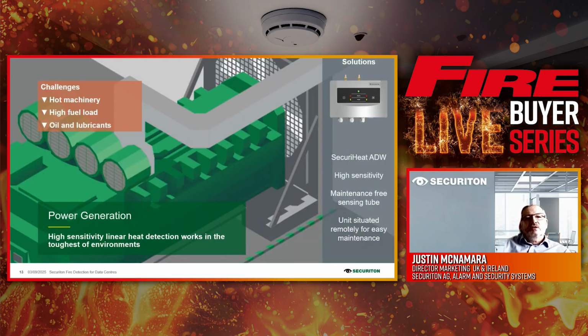There's also a challenge within power generation for data centers, usually a separate room or quite often a separate building. Within the power generation area, there may be hot machinery, a high fuel load, potentially oil and lubricants, and it might be that smoke detection is too late or inappropriate in that process.